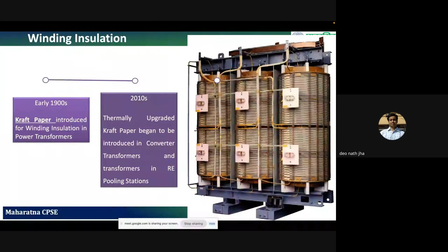So what is the advantage of these thermally upgraded papers? Kraft paper has a thermal limit of around 110 degrees. A transformer has an oil system and a winding system, and the more the loading on the transformer, the temperature keeps rising inside it. Once it goes above 110 degrees centigrade, failure can occur. But with thermally upgraded kraft paper, that temperature threshold increases up to 130 degrees. So the transformers can be loaded more highly and more variably.